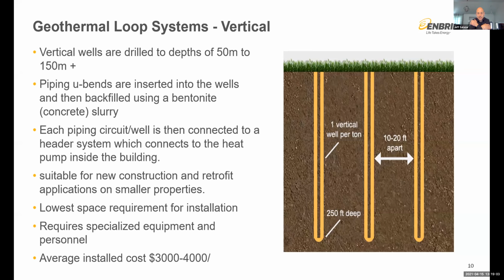And essentially what it is, is a 5 to 6 inch well hole that's drilled into the earth. And when the hole is drilled, the drill string is removed and a series of piping is put in, what we call a U-bend, which is basically a single circuit. And then once the well is filled up with that pipe, we backfill using a bentonite or a concrete type slurry that backfills and seals up that hole, which has two main purposes.